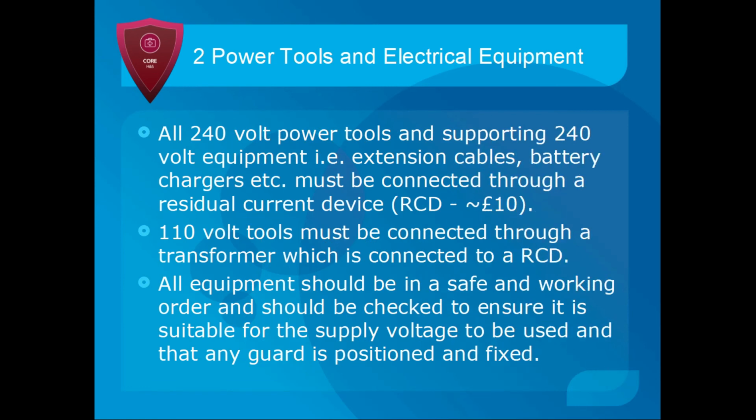Additionally, for anything that's connected to the mains, any extension cables, battery chargers, etc., must be connected through a residual current device, an RCD. Again, you can buy these online for about £10. They're not expensive. I doubt you'll be using 110 volt tools, but these must be connected through a transformer which is connected to an RCD in this case.